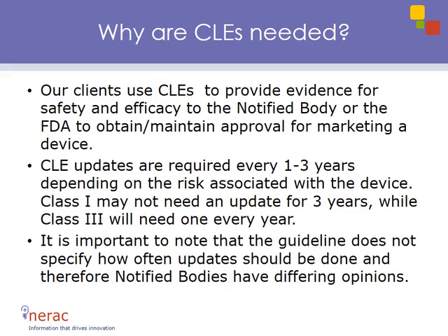Now, this is years away, but it's worth mentioning as it will include devices that historically did not require a clinical literature evaluation. Clinical literature evaluation updates are required every 1 to 3 years depending on the risks associated with the device. A Class 1, for example, may not need an update for 3 years, while a Class 3 will need one annually. It's important to note that the guidelines do not specify how often updates should be done, and therefore notified bodies may have differing opinions.